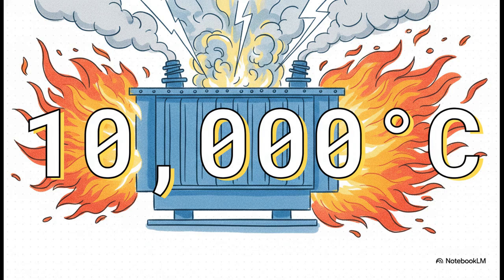To really get a sense of the stakes here, I want you to imagine 10,000 degrees Celsius. That's what we're dealing with. If an internal electrical arc fault happens, it literally vaporizes the transformer's insulating oil instantly, at temperatures exceeding that 10,000 degree mark. It essentially creates a literal ticking time bomb right inside the steel tank.